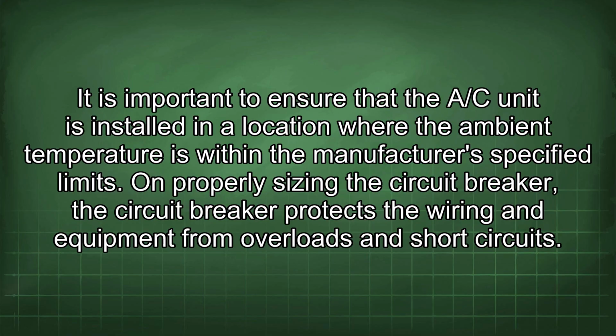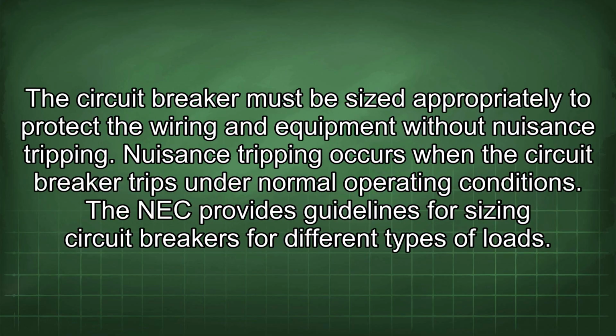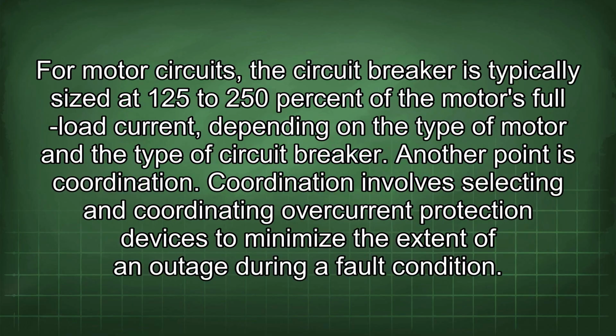the manufacturer's specified limits. On properly sizing the circuit breaker: it protects the wiring and equipment from overloads and short circuits. The circuit breaker must be sized appropriately to protect the wiring and equipment without nuisance tripping. Nuisance tripping occurs when the circuit breaker trips under normal operating conditions. The NEC provides guidelines for sizing circuit breakers for different types of loads. For motor circuits, the circuit breaker is typically sized at 125 to 250% of the motor's full load current, depending on the type of motor and the type of circuit breaker.